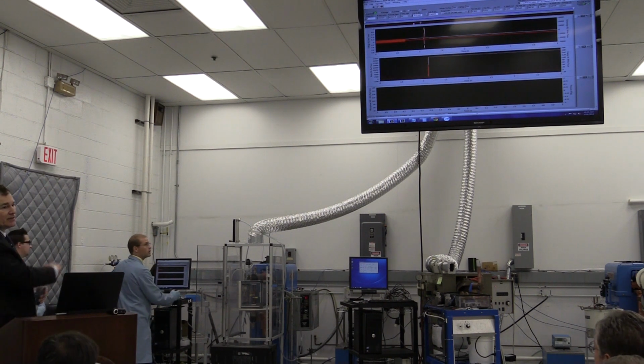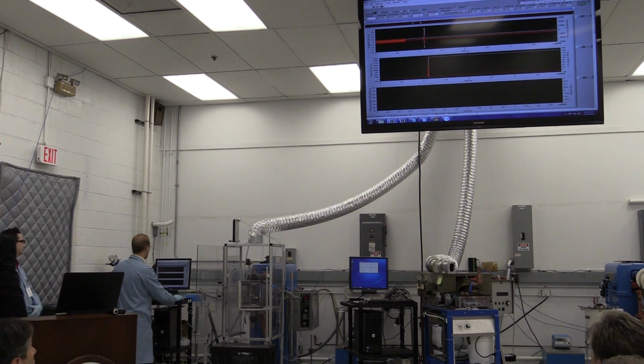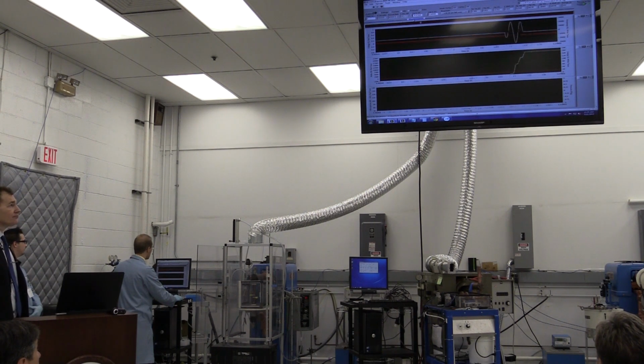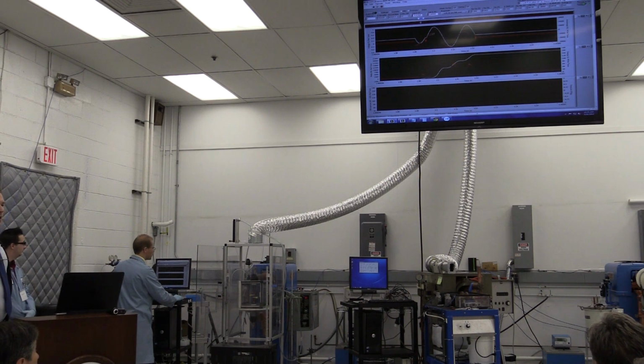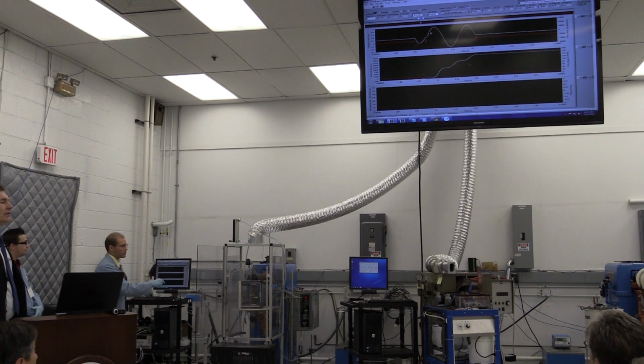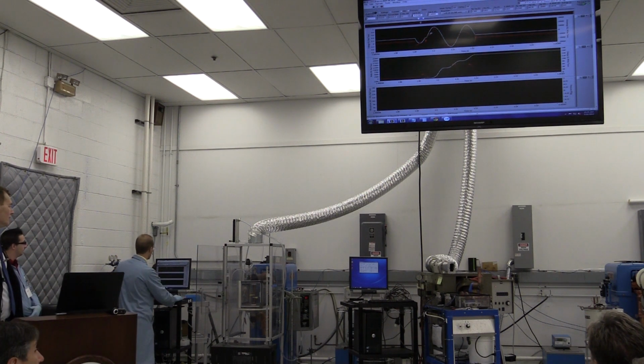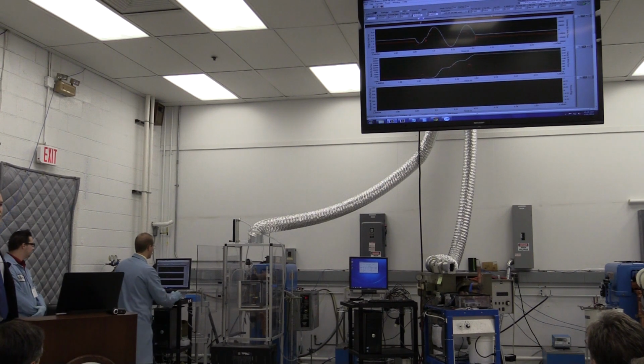So if you look up there, the current is very high. On the screen up there, this just acquired the waveform. And I'll zoom in. It recorded about 4 seconds, and the pulse here is only about 30 milliseconds. And the white trace is the current, and the red trace is the measured voltage. And there was just a little bit of deviation from a sine wave here because there was some contact resistance, which caused a little bit of a brief deviation from that sine wave.